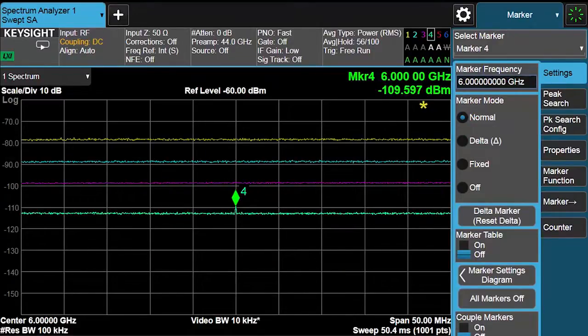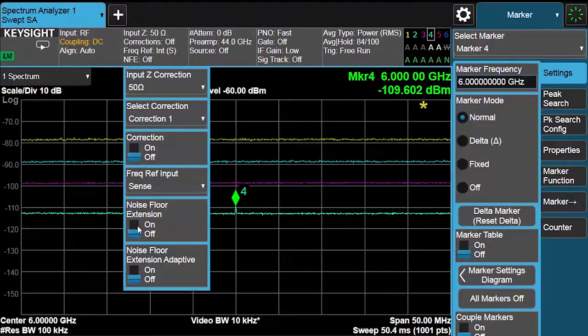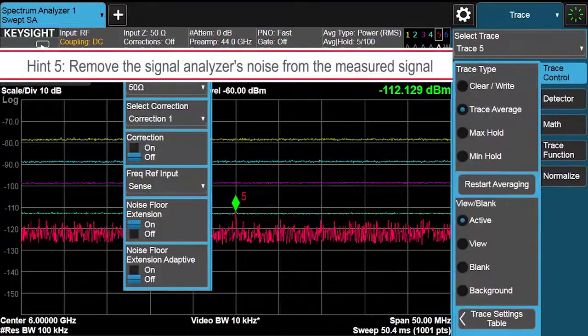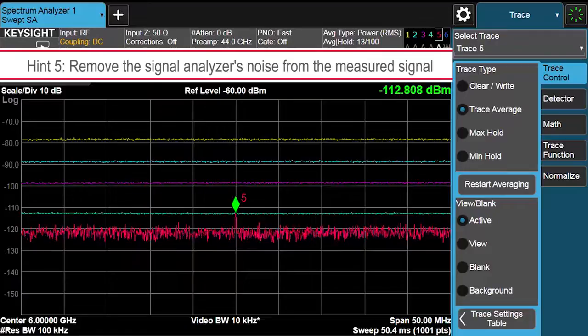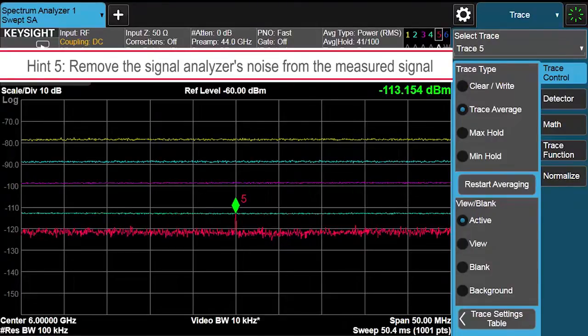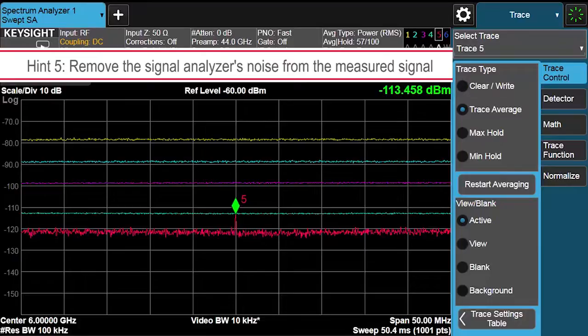To even further improve your sensitivity, you can use a feature that is unique to Keysight's X-Series signal analyzers, Noise Floor Extension. I'll go ahead and turn that on. When using Noise Floor Extension feature, you can actually subtract the noise contribution of the analyzer from your measurement real-time. The instrument stores internal algorithms that are applied and automatically updated even if you change your settings, including frequency, resolution, bandwidth, span, and even detector types.